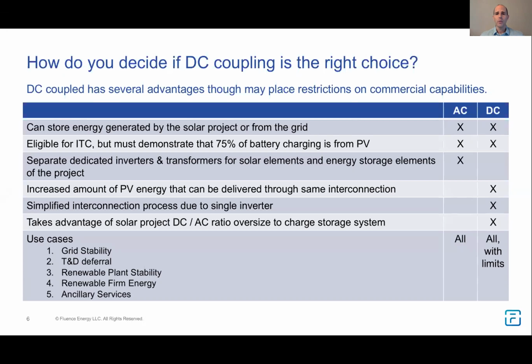On the DC side, one of the advantages is the ability to increase the amount of PV energy that can be delivered through the same interconnection. I'll touch on that more in the next slide, but the idea is essentially you can overbuild the DC portion of the plant and get more energy out through the same nominal number of megawatts.